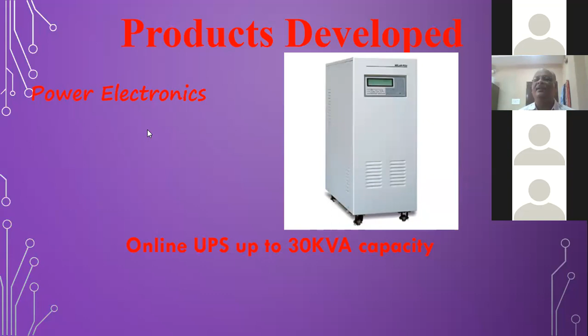Next is from power electronics. This is a special requirement of telecom, an SMPS rack-featured system where 25 amp modules are inserted and removed, allowing parallel operation, a hot standby system. These things are required according to the specifications given by TEC. I could achieve that, so this comes into my account.